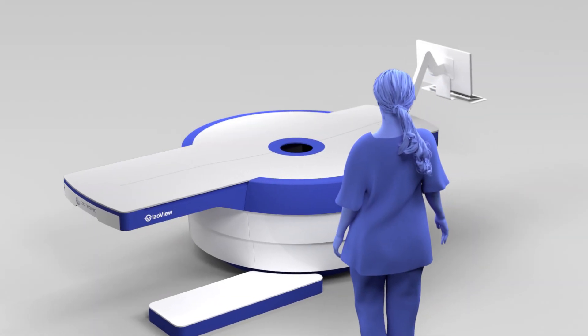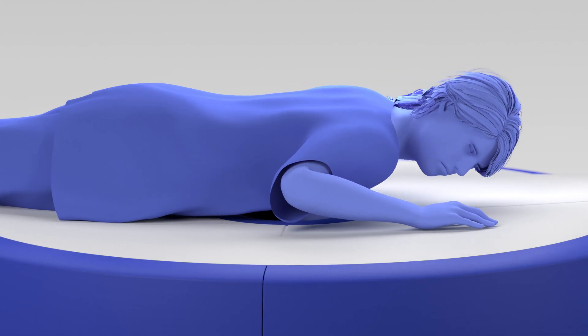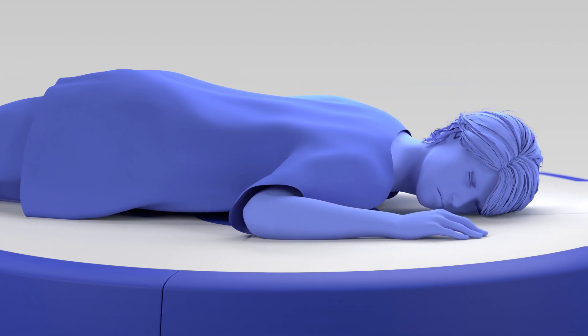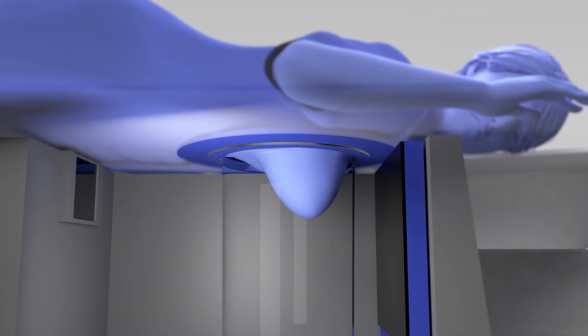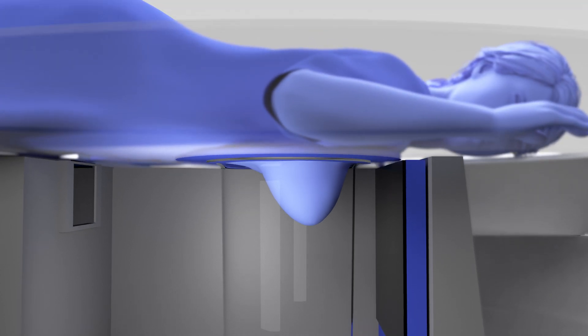Unlike traditional imaging, the patient is in control, independently placing themselves in a comfortable position for scanning and virtually eliminating the need for constant breast handling by the technician. The breast hangs through the aperture naturally without any painful compression.